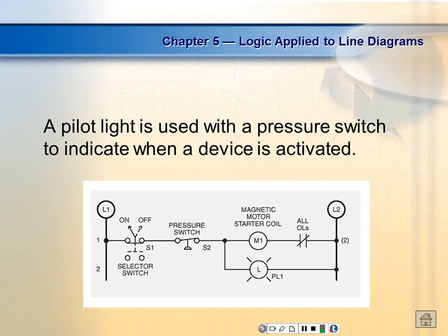So that two over there is referring to that pressure switch? No, it's referring to the contact being controlled by that relay. Okay, understand? And it's going to be in line 2, and there's no contact down there. So that's a mistake. Is that in y'all's book like that? Yes. Well, they left out something because here's line 2 right here. So we follow line 2 over, and all it goes to is a light bulb. So this is wrong.